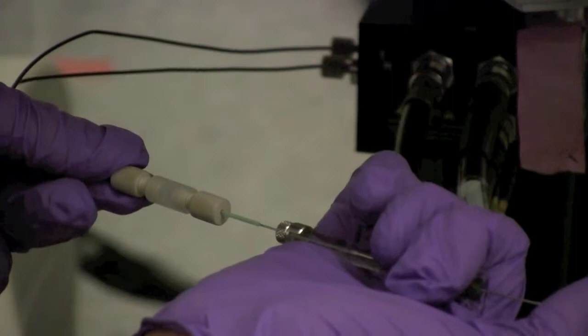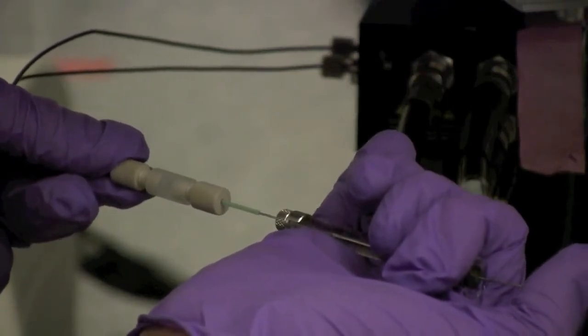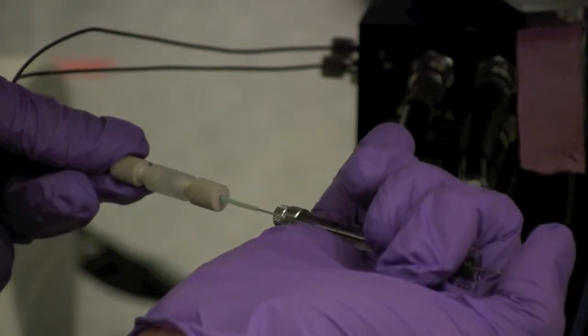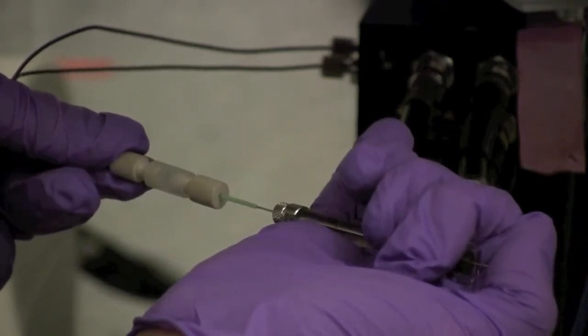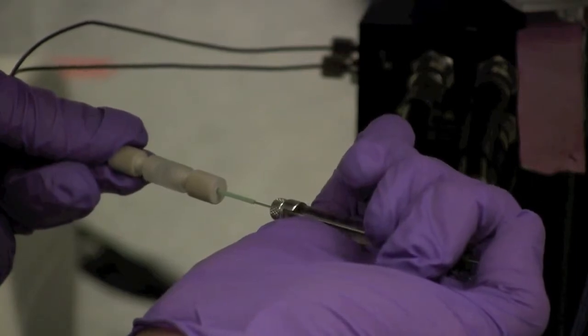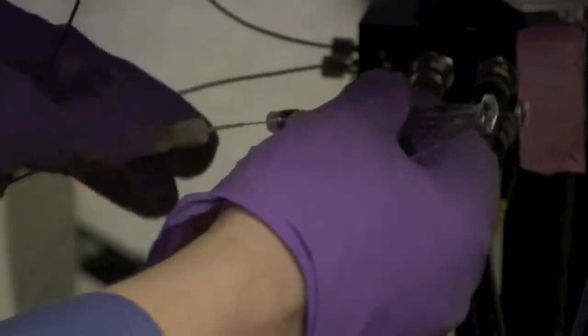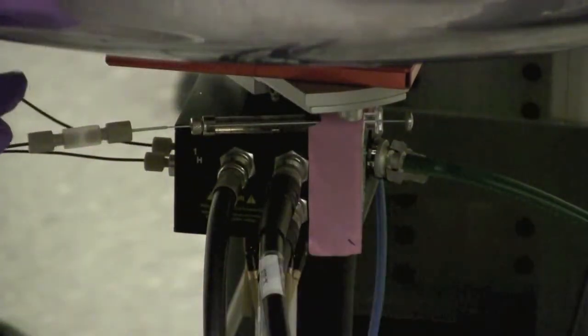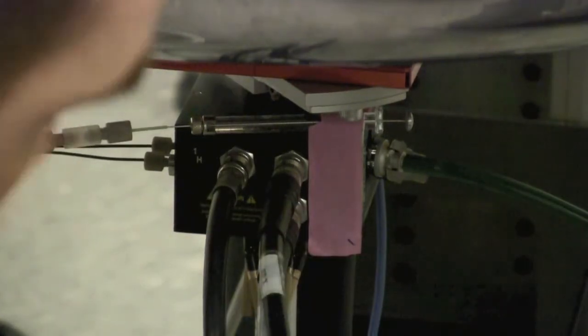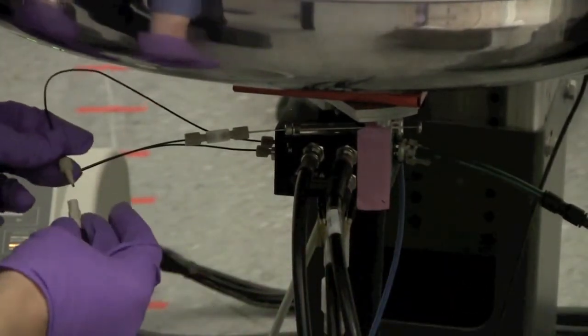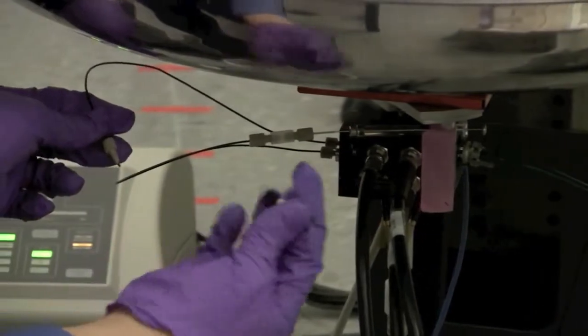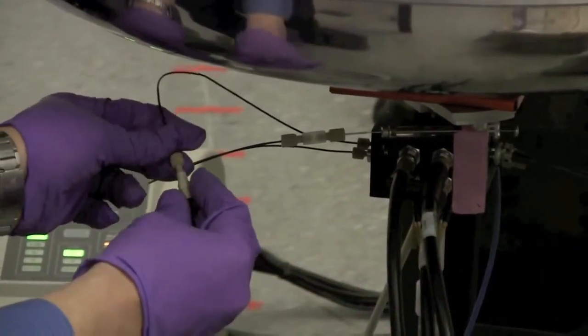So I'm just going to carefully, slowly push the sample into the probe. And if all goes well, we will have filled the probe. And this little piece of tape here is so that we can just keep the syringe there while we run. So you can just put it like that. And as surprising as it is, your sample can evaporate back through the line. So if you're running for an extended period of time, it's good to put a cap. I've made a cap out of a plug and a union here onto the outlet.